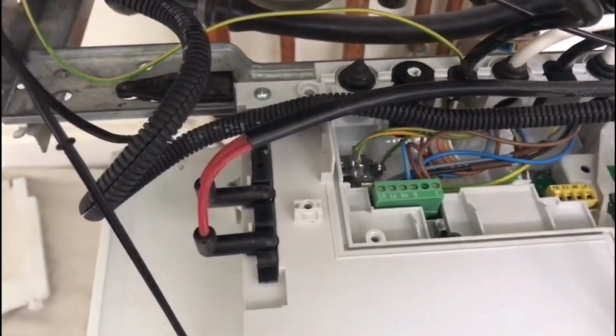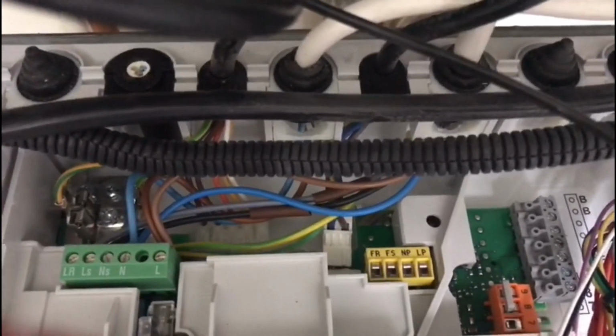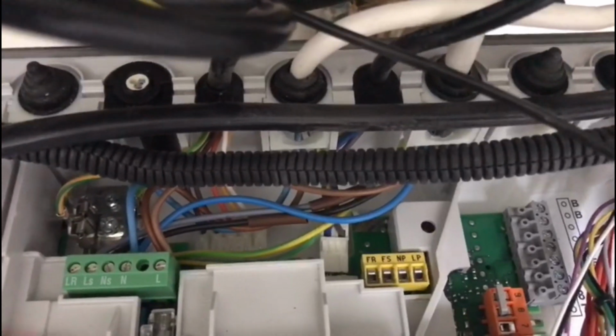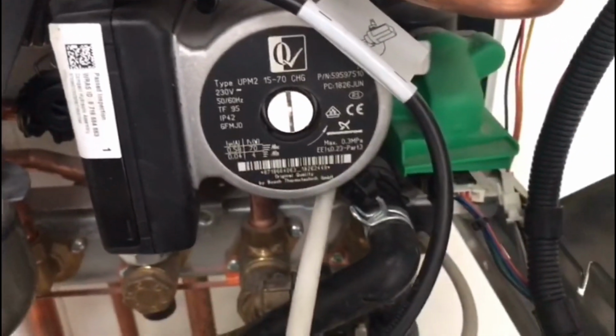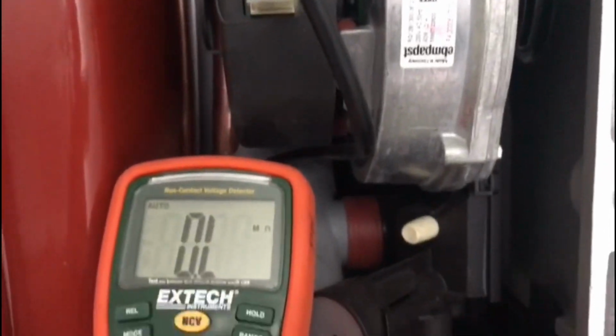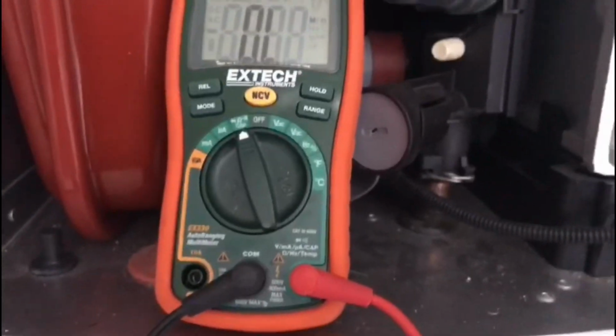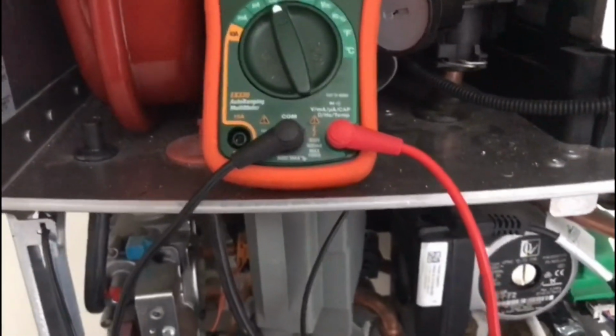That means that live is finding a path down neutral, normally shown by evidence of arcing all the way around your components, like your fan plug, your pump plug, all the way around your circuit board. Any sign of scorching or electrical marks would show you that you're having a short circuit somewhere. Something's touching. It could be two wires which are melted together on the fan. Check things like your fan plug and your pump plug, anything which doesn't look quite right. Let's say something's got wet on your plugs, for example, on any component of the boiler. Best to check it when it's dead rather than when it's live, because you don't know. But doing this test is the way to know that you've got a short circuit on some components somewhere.